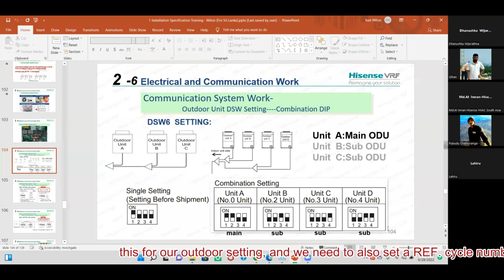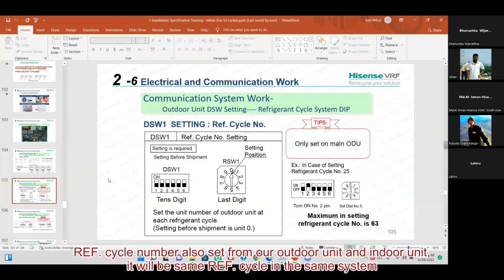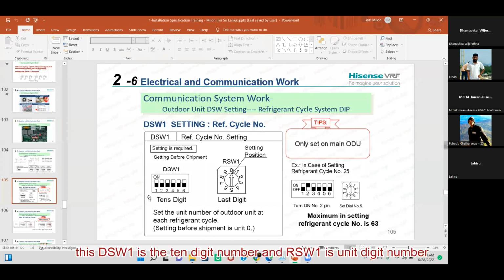This is for our outdoor setting, and we need to also set the refrigerant cycle number. The refrigerant cycle number is also set from our outdoor unit and indoor unit. It will be the same refrigerant cycle in the same system. DSW1 is the ten digit number, and RSW1 is the unit digit number. With this we can set a maximum of 63 refrigerant cycles.